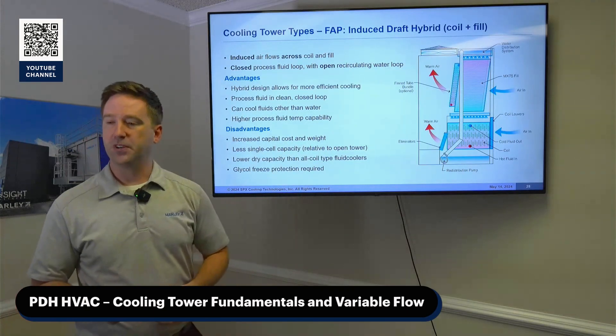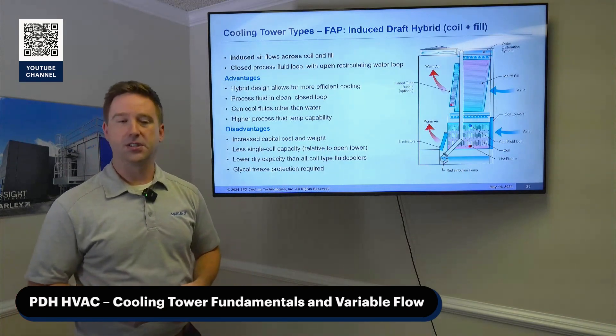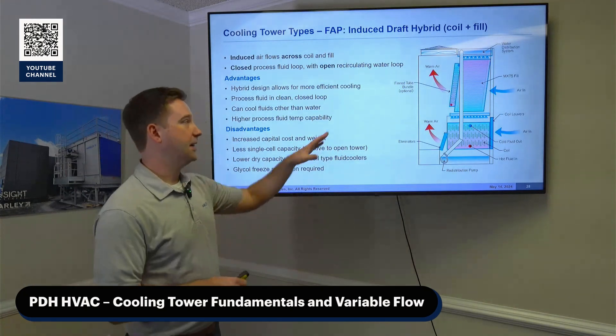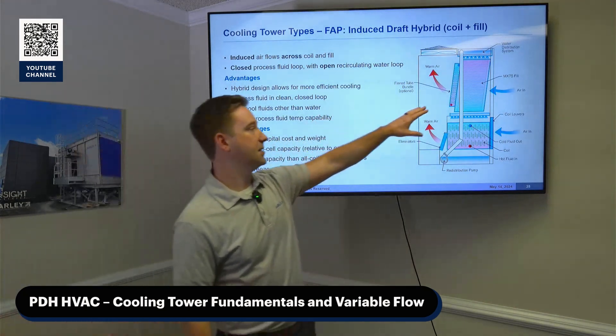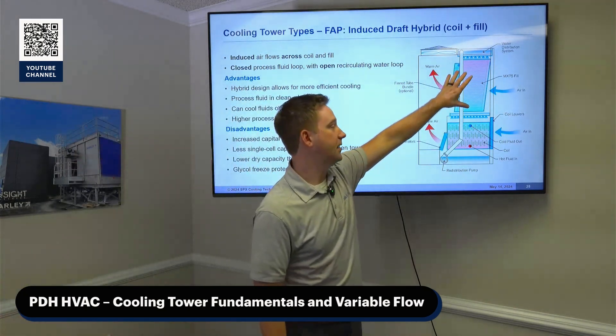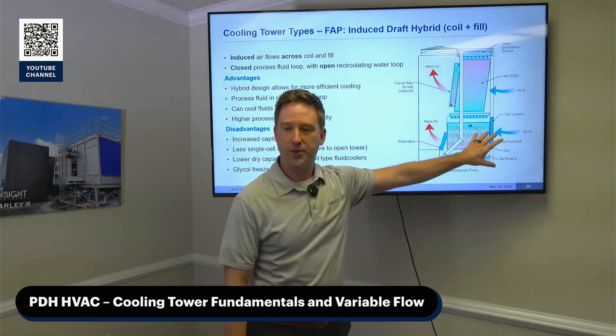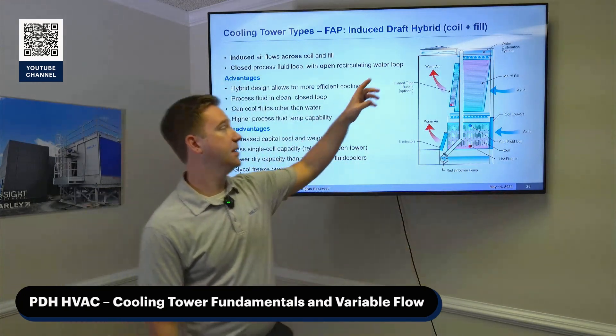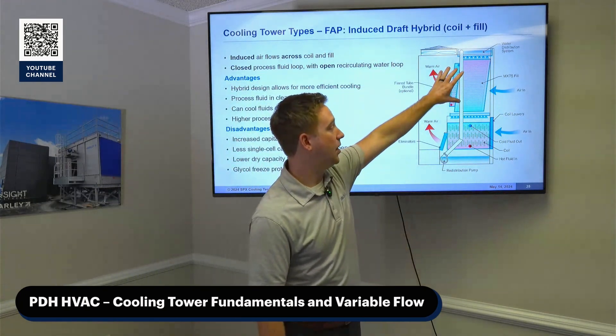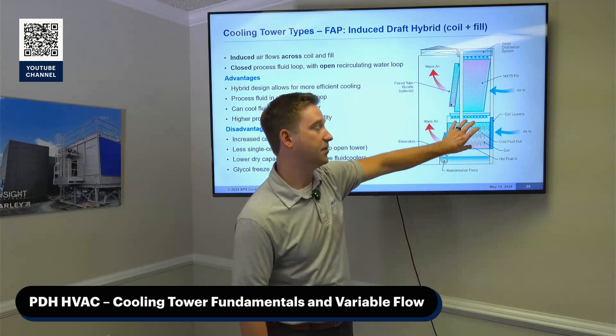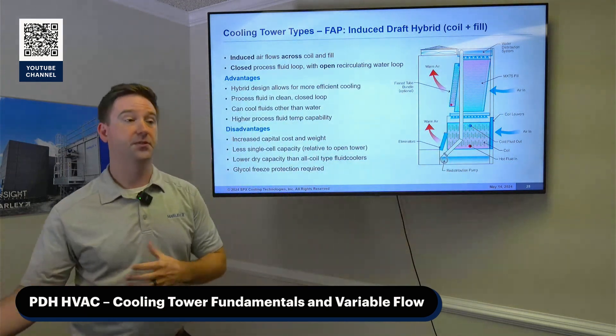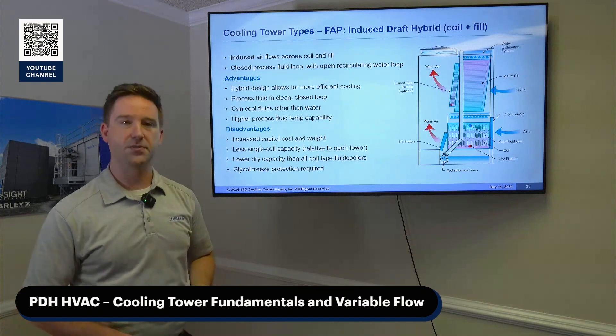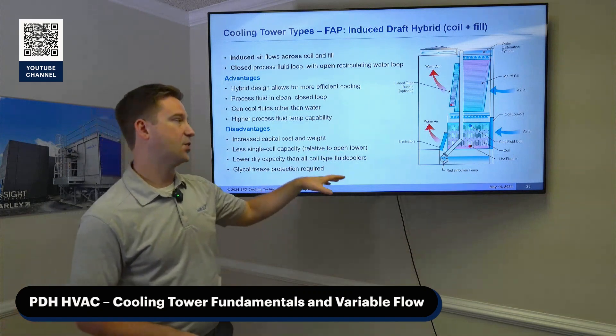If you want to be more efficient than a straight open tower or a basic fluid cooler, there's a hybrid option. It has both heat transfer media and a coil inside the tower. It recirculates water, cools it over the heat transfer media, and then passes it over the coil which contains your process fluid — indirectly cooling your process fluid in that coil.